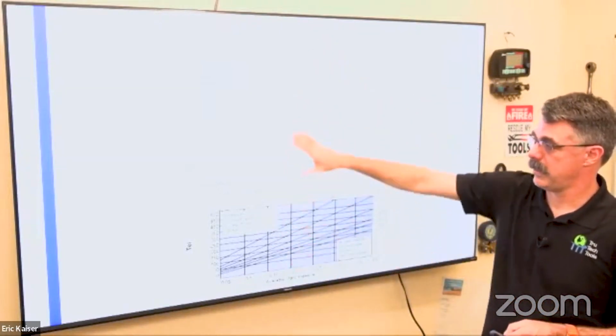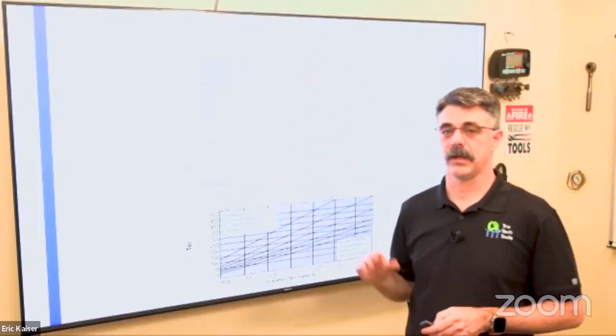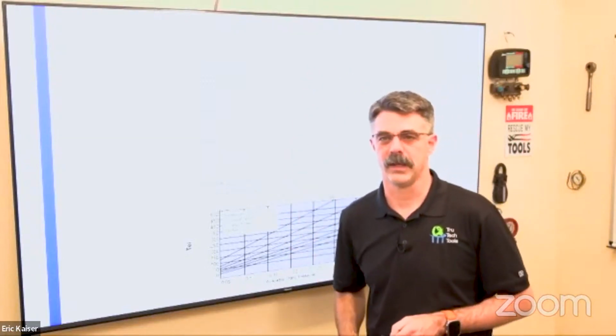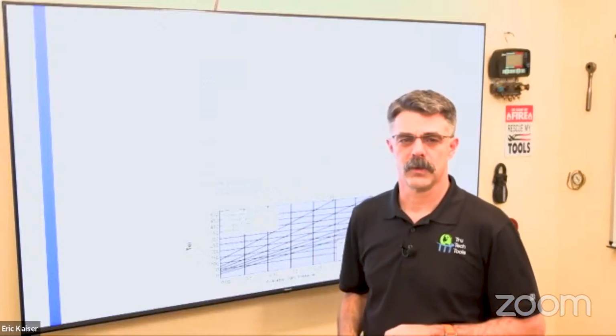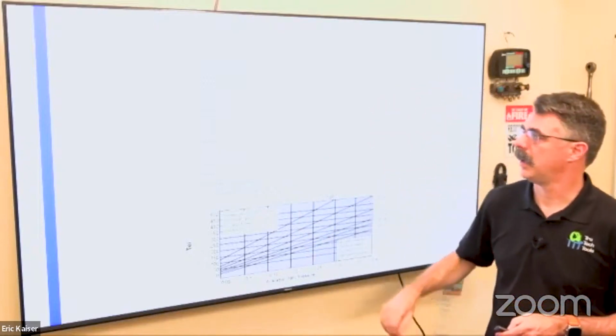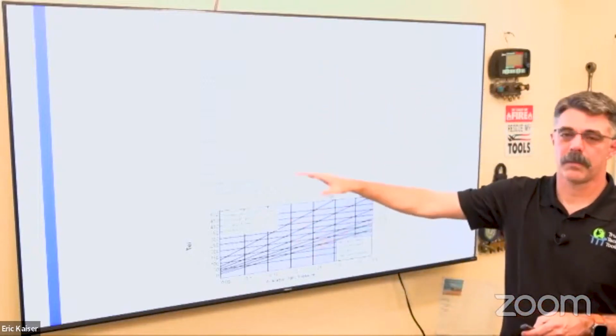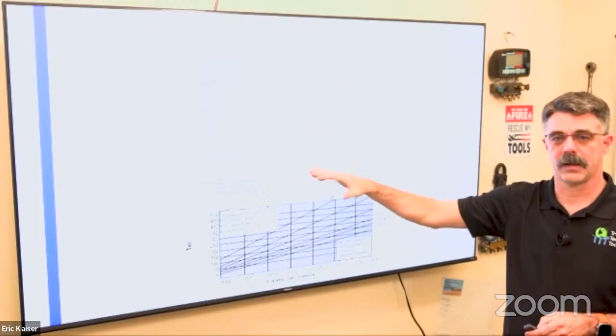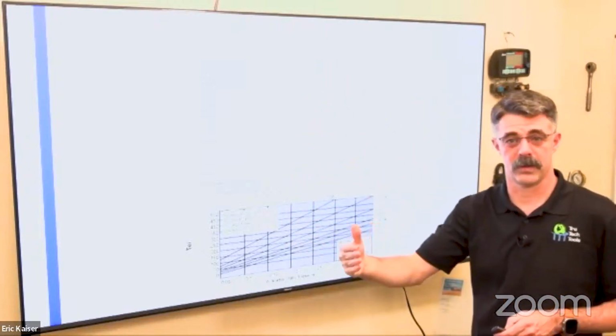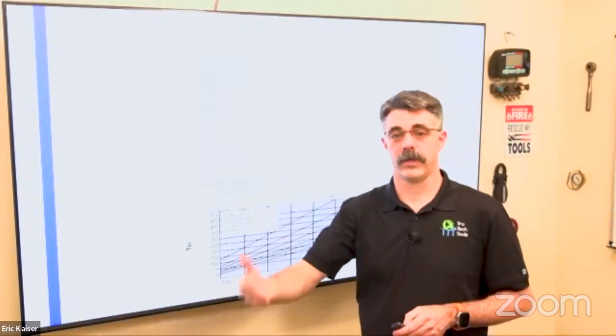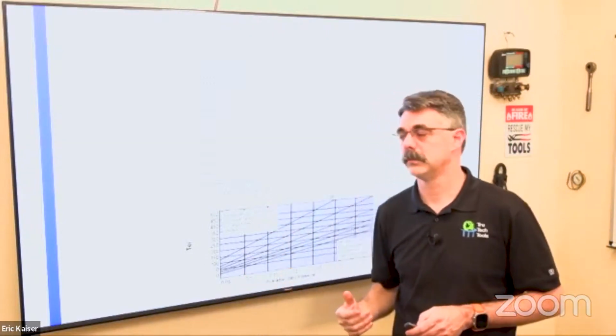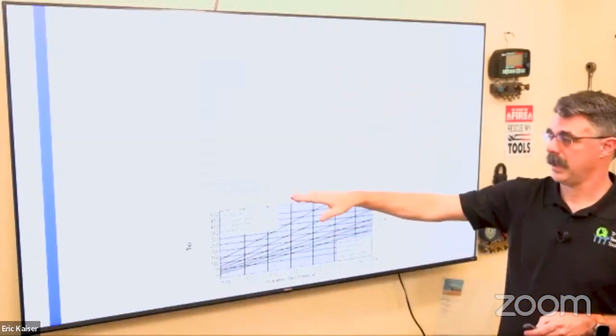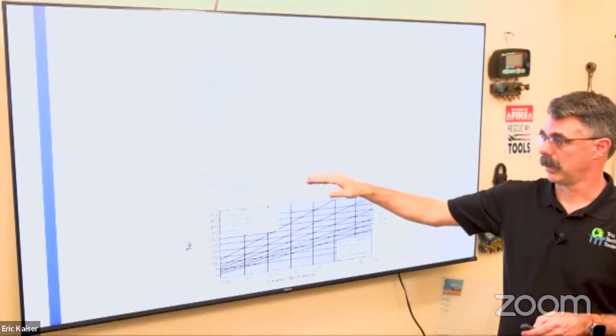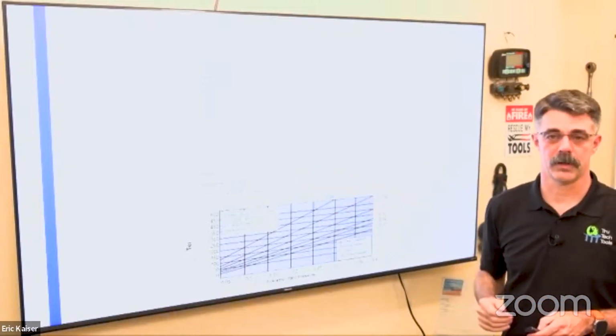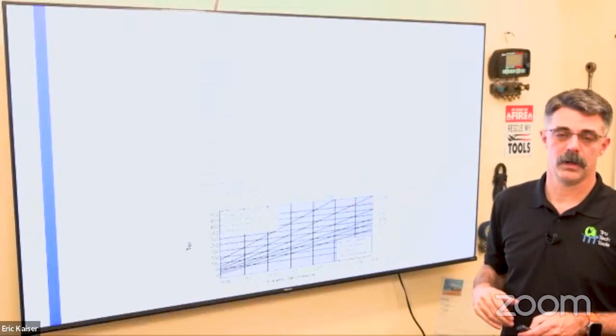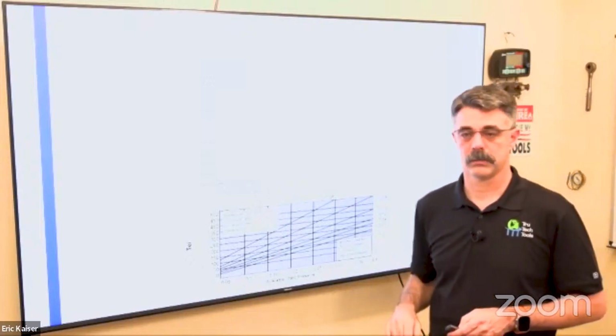This is the friction rate worksheet out of Manual D. This is a really, really handy thing to have. And if we use this properly, this tells us how much static pressure we have left over for the ductwork from all the other components that are in there. So we run that down, it gives us a friction rate, or the available static pressure, from our unit. All right.